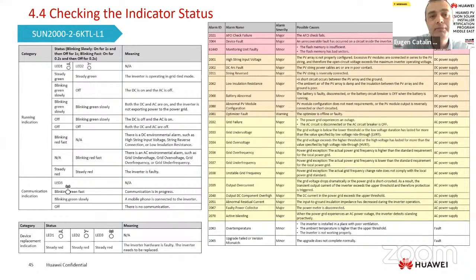I want to do something on the inverter and it's not working, but the LEDs are completely off. So what are you trying to do if the LEDs are completely off? This is when the inverter is completely off. You will not manage to do anything. So let's first check why the LEDs are completely off, or if the LEDs are completely red, this means a fault, an installation fault or something, or the inverter itself is faulty. So as you can see, the LEDs are important.